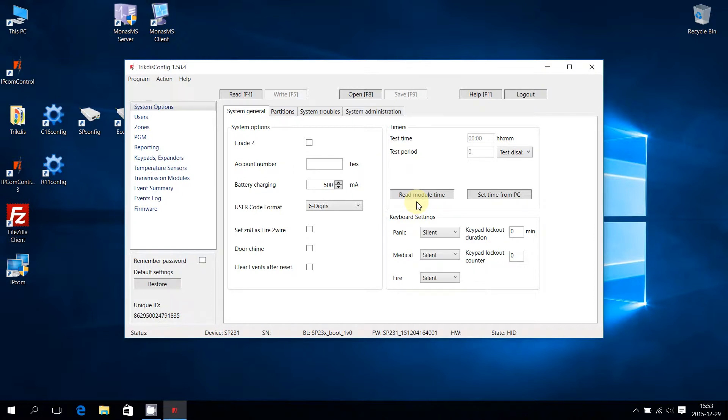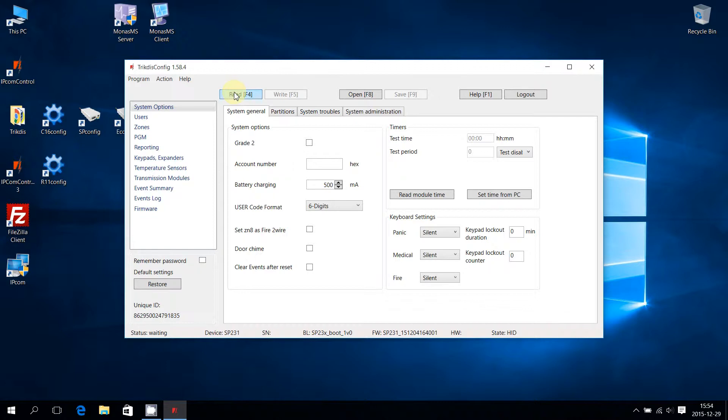In order to change the existing SP231 parameters, they must be read from the control panel. Press Read F4 to read the current parameters. Once the parameters are read, the status on the bottom left corner will change to Done.